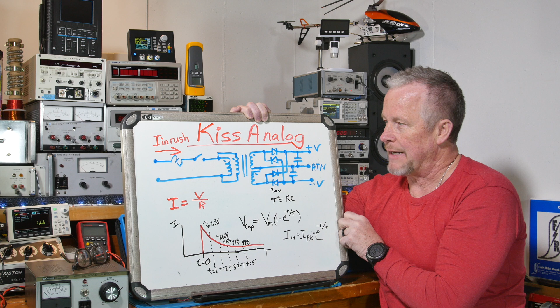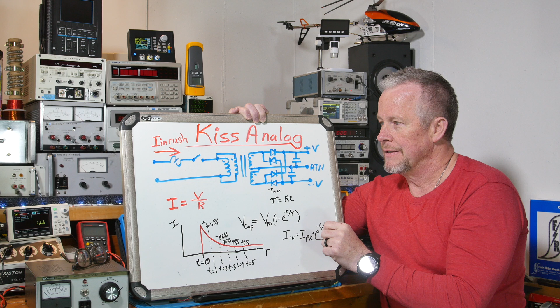You get 120 pulses on each one of these caps, but each pulse is about 8.3 milliseconds long. So depending on where we happen to hit the switch on that waveform is going to depend on how much current we see on that first inrush.